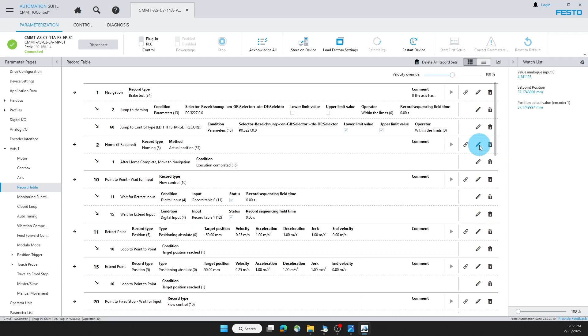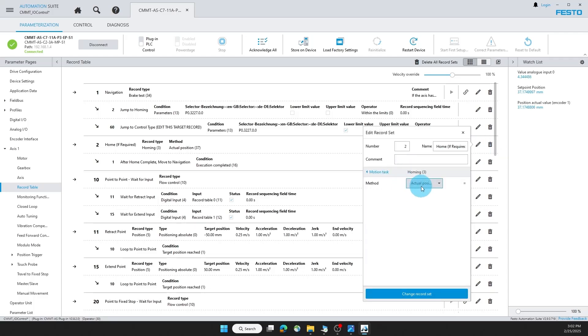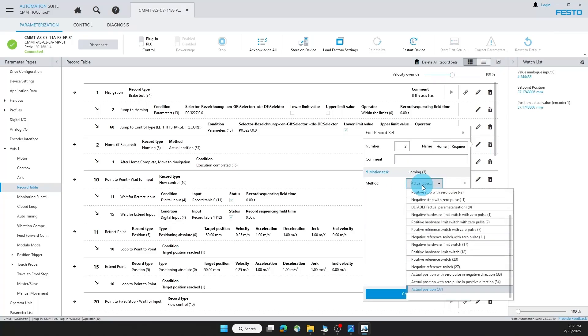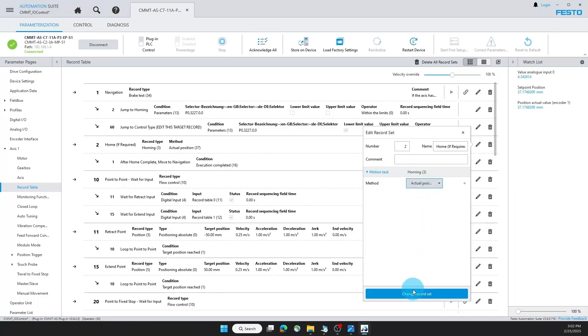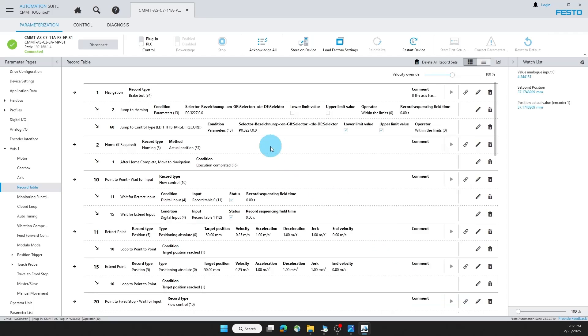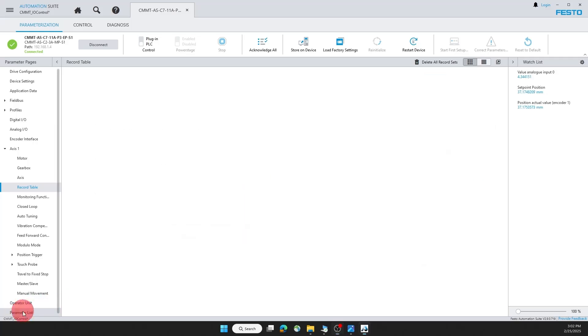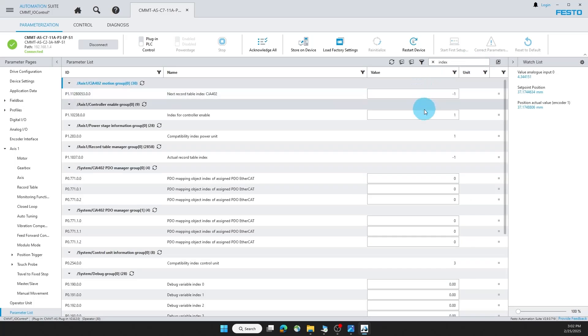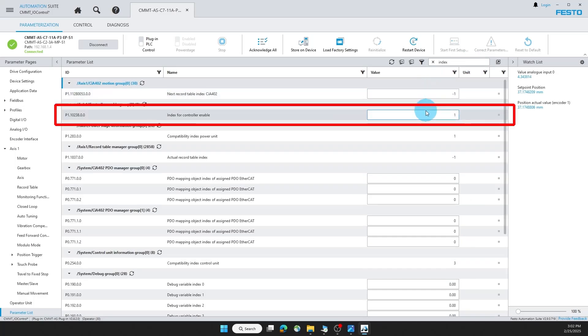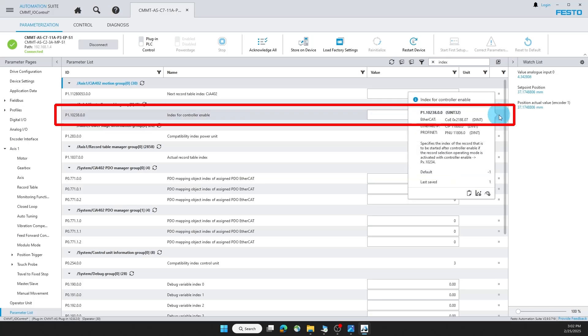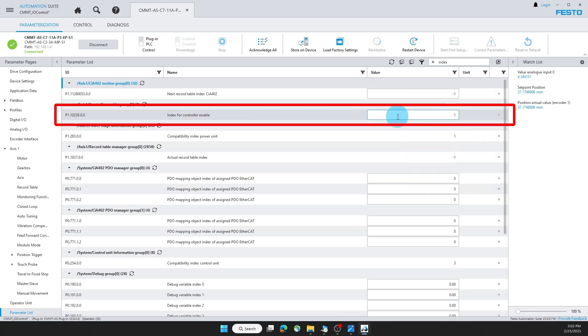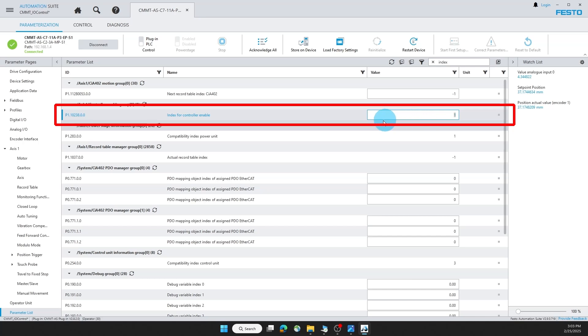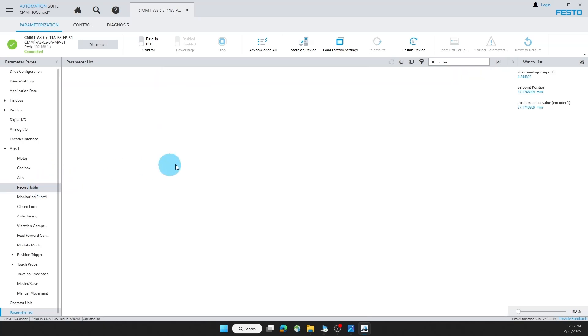With this pencil to the right I can edit that. I'm going to leave it as actual position for now, but you can change for your application. Let's say you want to home every single time the motor is enabled. What you can do is under parameter list, you can search for index. In this index for controller enable, this is set to one for this program, but if I change it to two, this will make it so that the motor will home every single time it's enabled. Let's go back to the record table.